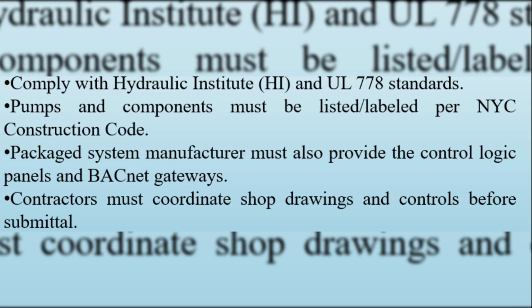Contractors must also provide complete nameplate data for every pump and drive. Another key point is coordination. The HVAC contractor, controls contractor, and pump vendor must coordinate closely before any submittals can be approved. And when it comes to packaged pumping systems, manufacturers are required to provide their own control logic panels, complete with BACnet cards, to ensure seamless integration with the building management system.